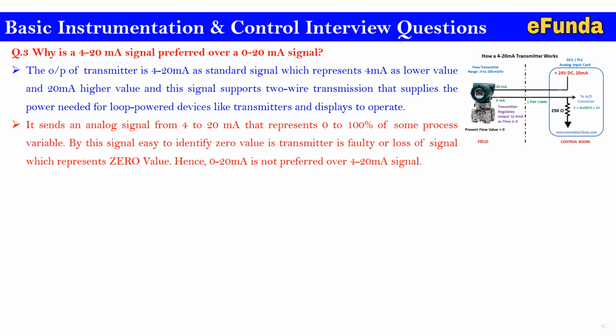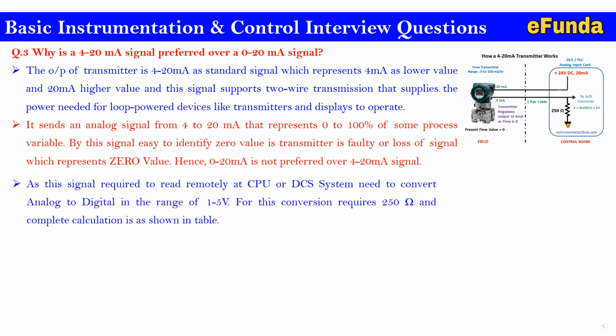With this signal, it is easy to identify that a zero value means the transmitter is faulty or there is loss of signal. Hence, 0 to 20 milliamp is not preferred over the 4 to 20 milliamp signal. As this signal needs to be read remotely at the CPU or DCS control system, it needs to be converted from analog to digital in the range of 1 to 5 volt, which is compatible with the DCS or PLC analog input card. For this conversion, it requires 250 ohm, and the calculation is shown in the table.